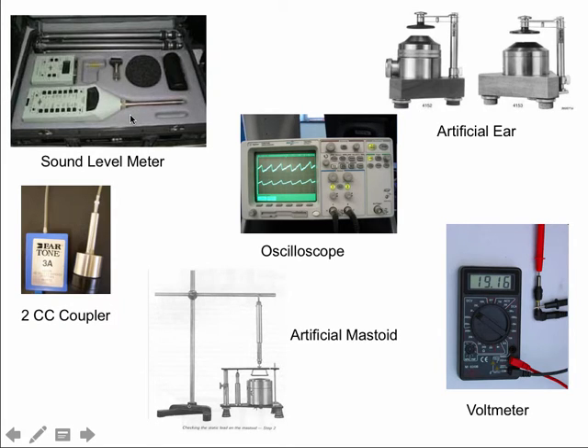These are one of those classical analog sound level meters, which are actually huge and heavy. But until recently they were used predominantly. Now with the digital age, the equipment has reduced in size and weight. Some of you might have seen this around. This is an oscilloscope. Essentially, it depicts the input signal in the form of a waveform. This might be something that you use for calibrating the rise and fall time of your signals, of your pure tones. And sometimes you might even use it as a frequency counter for frequency calibration.